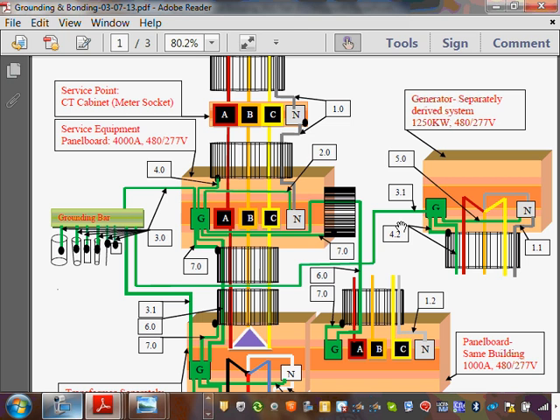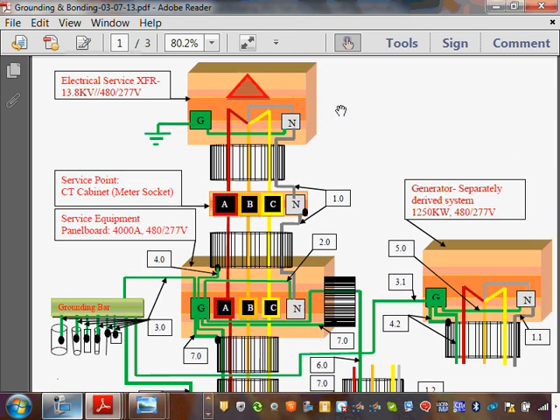Okay, so any comments, guys, about grounding and bonding the system? So it seems we have smokers here. Here you go. So we summarize: we grounded the system, we grounded the equipment, we tied the two together through the main bonding jumper and the neutral. Any comments, guys, any questions? What I summarized in this 1 hour is basically 2 chapters, almost 4 chapters in that book: grounding a system, grounding at the service, grounding electrode conductor, and main bonding jumper. Of course, the devil is in the details. They show a lot of equipment that you can use.